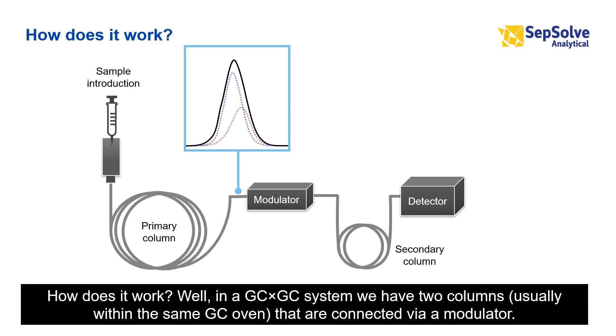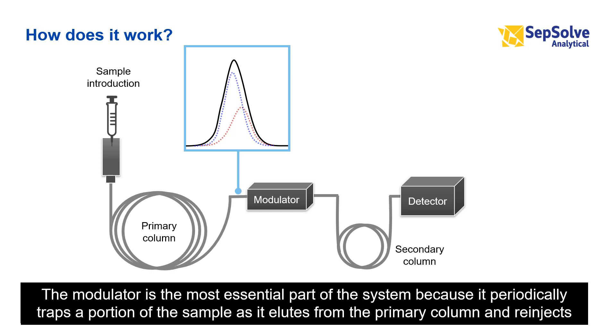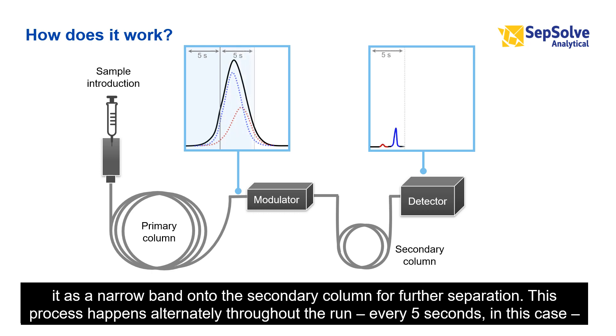How does it work? In a GC×GC system, we have two columns, usually within the same GC oven, that are connected via a modulator. The modulator is the most essential part of the system because it periodically traps a portion of the sample as it elutes from the primary column and re-injects it as a narrow band onto the secondary column for further separation.